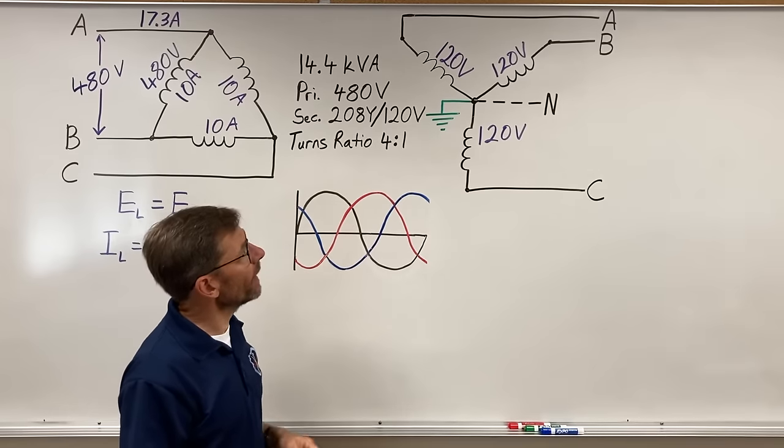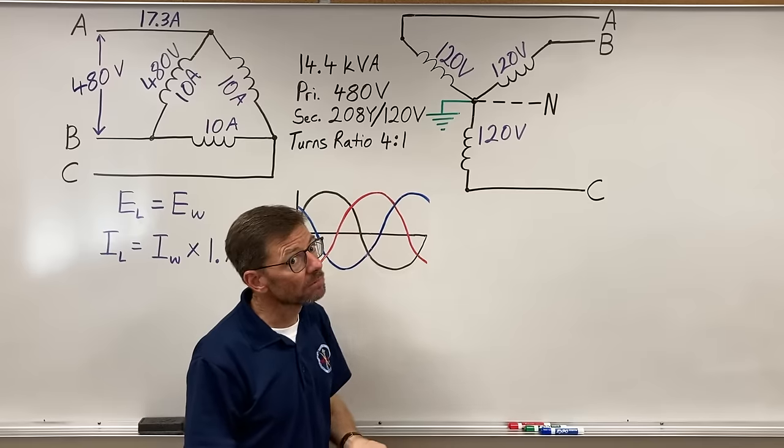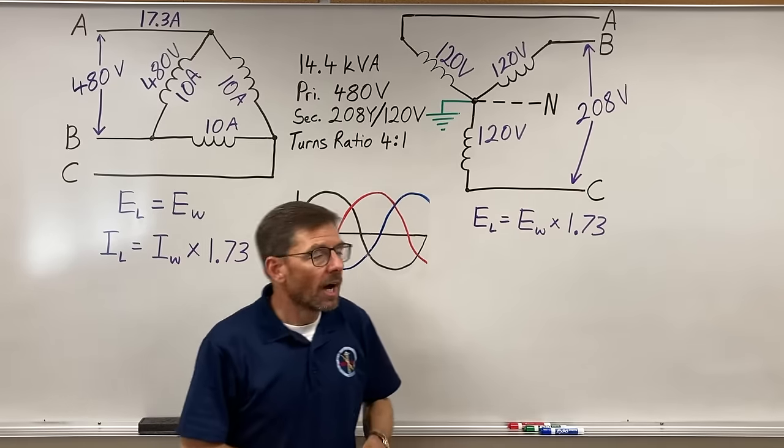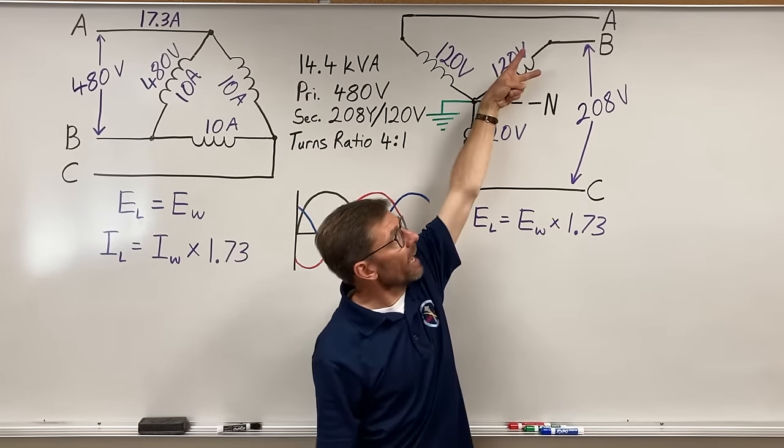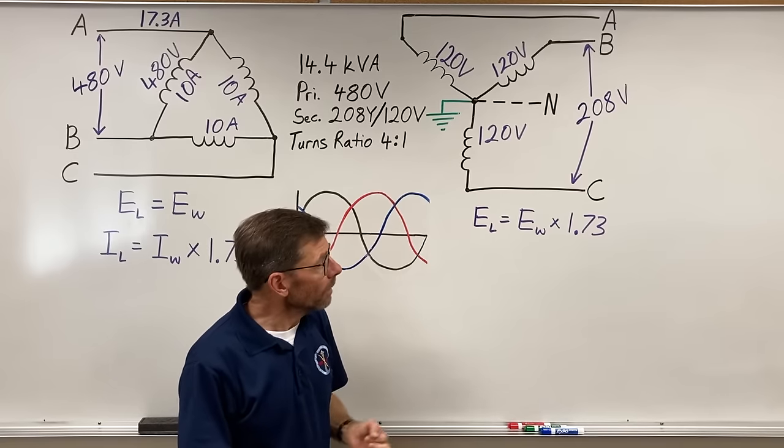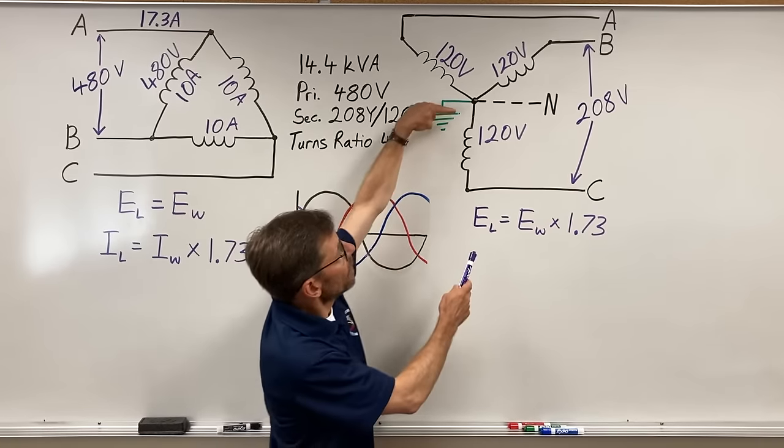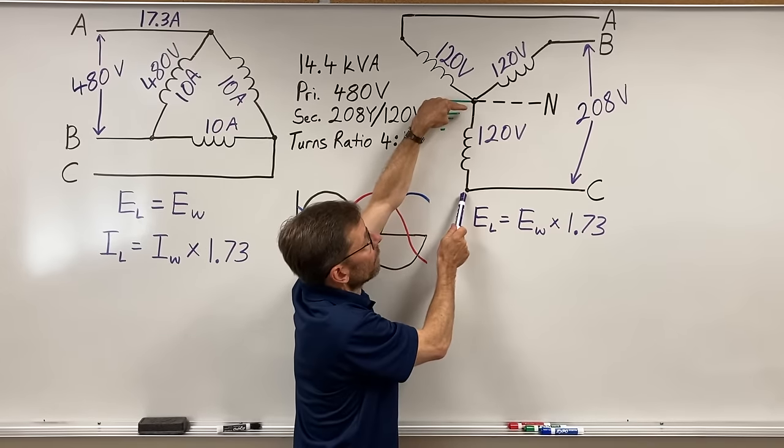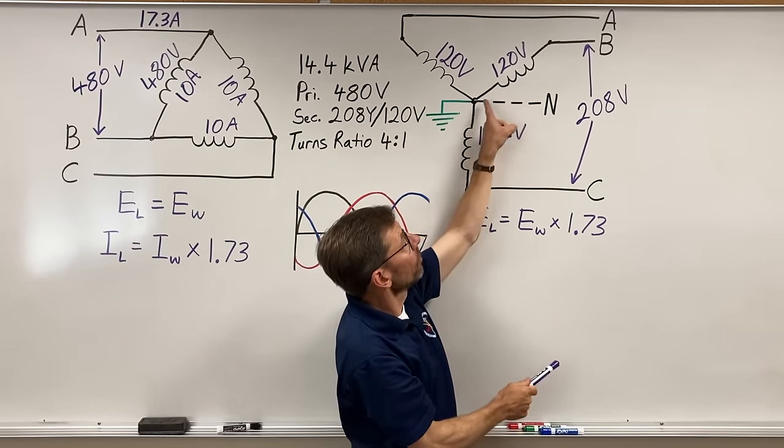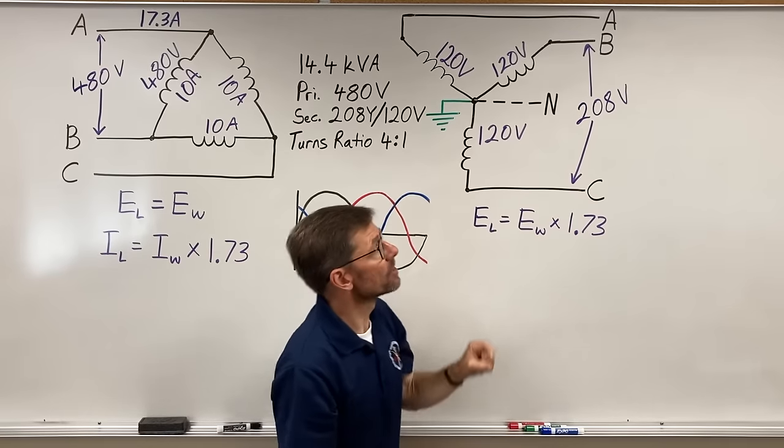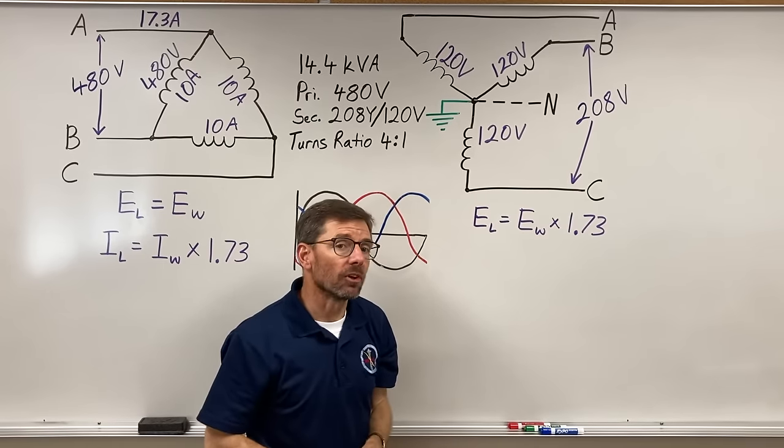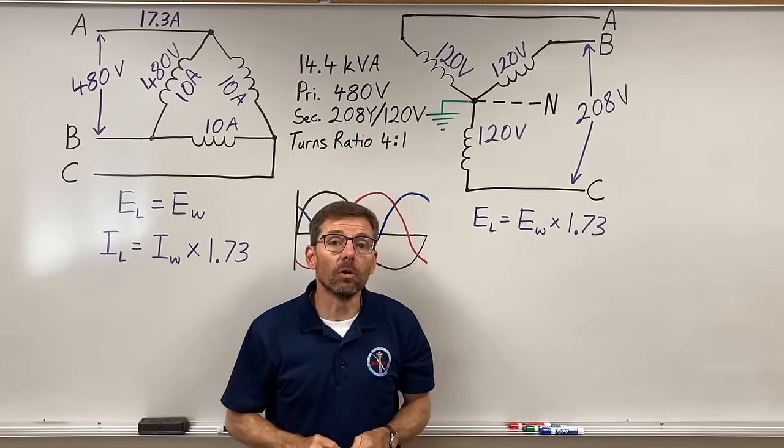Where does the 208 come in? If you'll notice, the 208 is indeed 120 times 1.73 yields 208. I just drew it between B and C, but between A and B, and also between A and C, I'm going to have 208. And why is that? Well, the 120 volts is between the neutral, the neutral point, and the phase. 120 volts neutral to C phase. 120 volts neutral to B phase. And neutral to A phase is 120 volts. That's how we power our receptacles and other 120 volt loads.